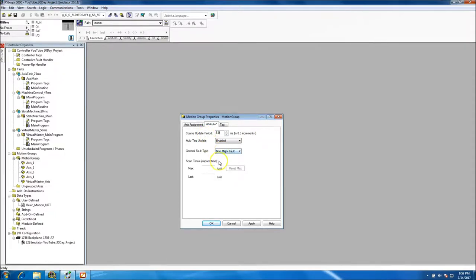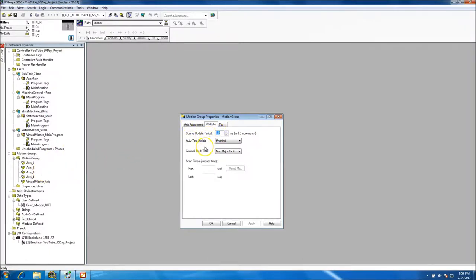In our instance, we want to set it at five, or six to give ourselves margin and make sure it updates fine. If this were a real-time-critical application I'd keep it tighter. The coarse rate update is the time you're getting information back from your process and servos. In a Logix 5000 processor the hierarchy is: motion first, then I/O, then logic.